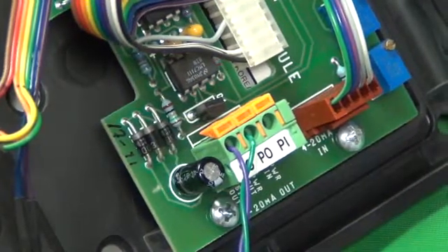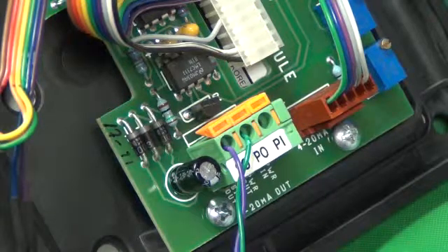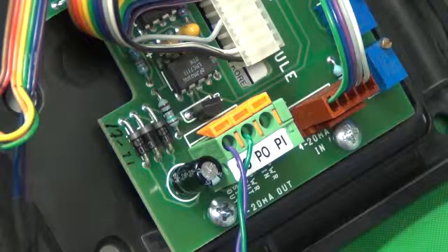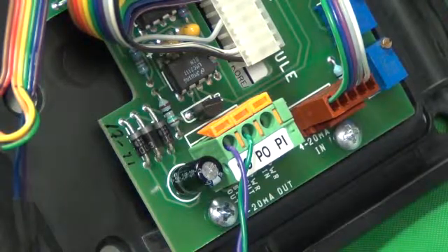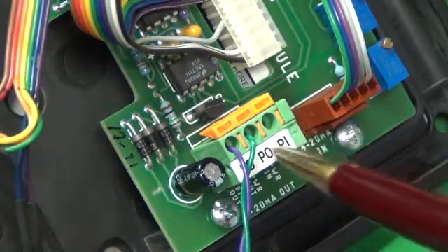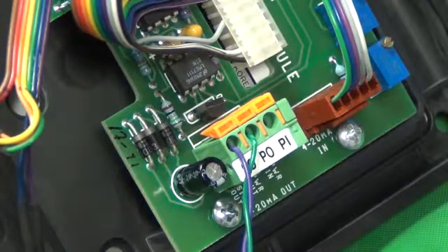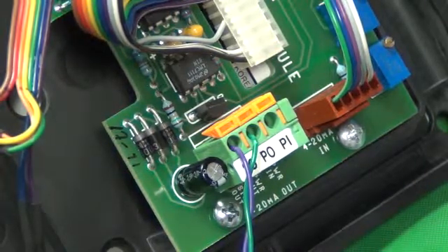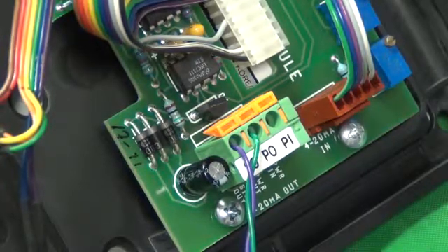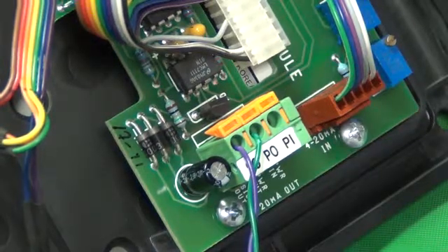I think it would be interesting for us to look at how the controller communicates with the pump. The LMI pump has an optional 8-wire cable, which we're using in this case, and we're using the green and the violet wires only. The other wires are not used. Typically they're used for powering other equipment, alarm outputs, or flow pacing input. In this case, neither one of those is needed.